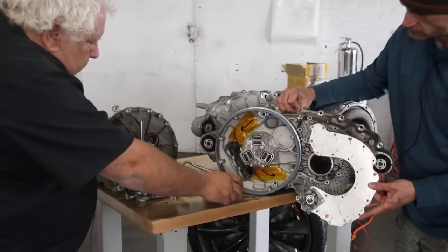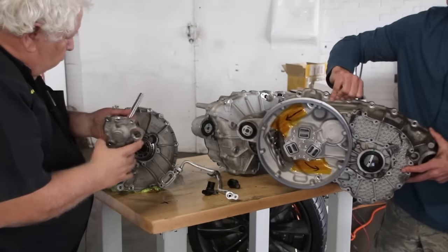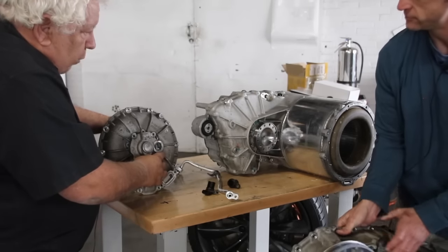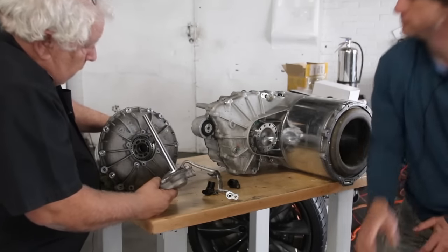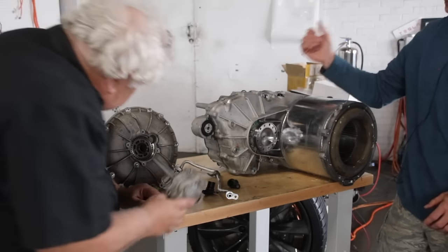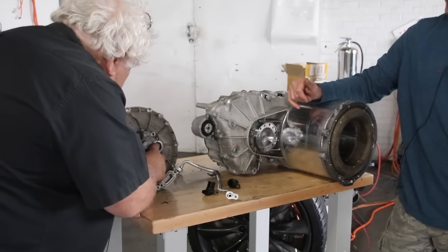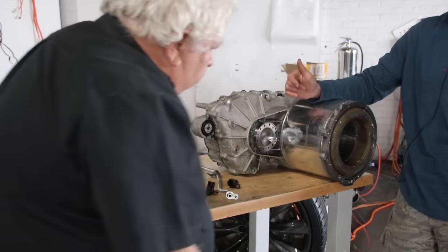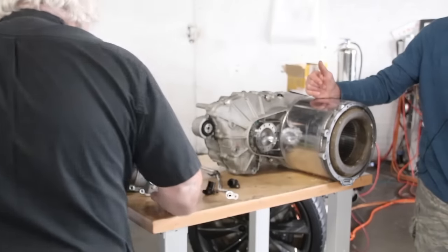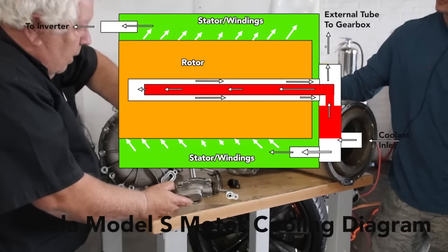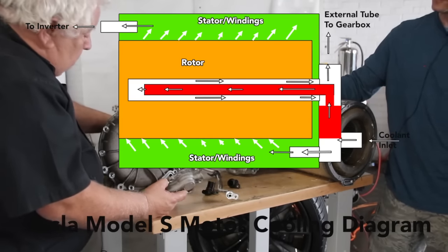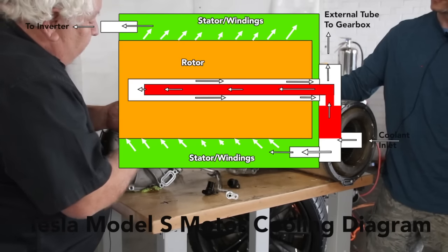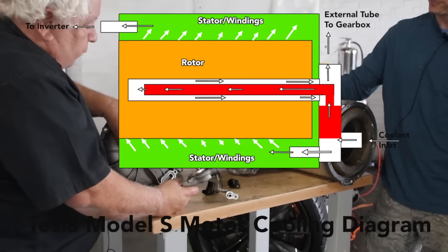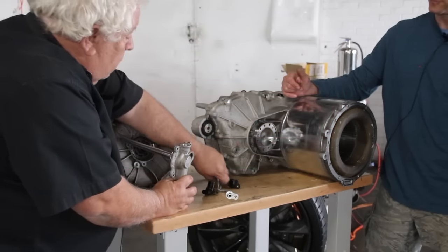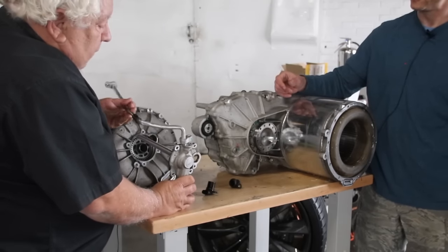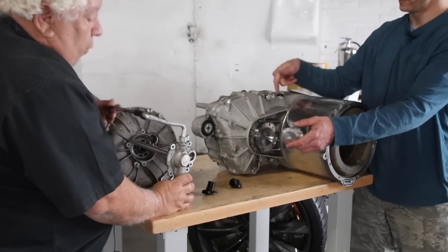So that's the cooling. Now the interesting thing is we go through this tube down into the rotor, and then we come back. The fluid goes down the middle of the rotor, which sits in here, and it just terminates - the tube is not as deep as the tube it sits in, which is larger diameter. It comes back and seats here with an O-ring, so the fluid goes through the rotor and back out the top, which is where this external device is connected, and then over to the other part.